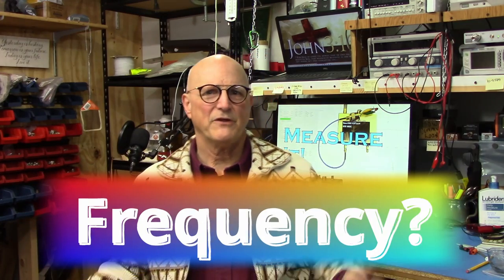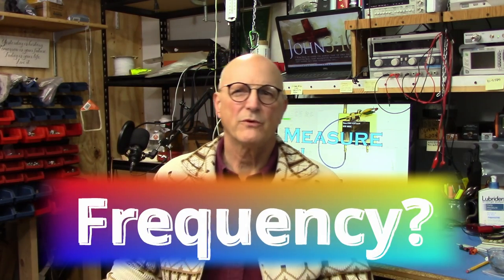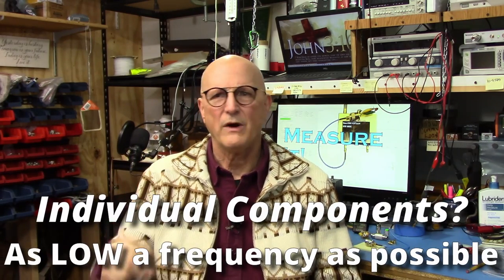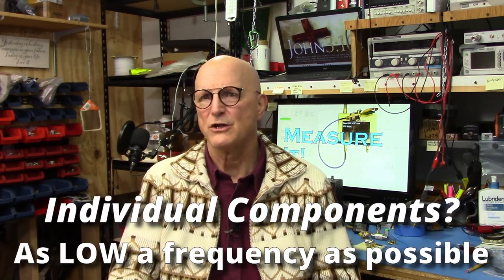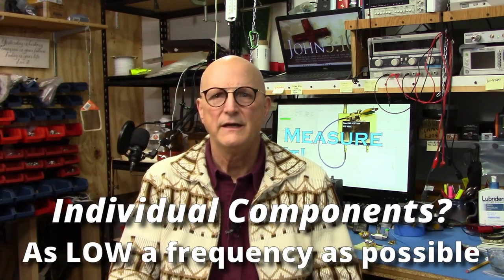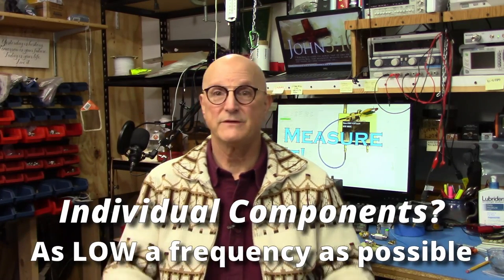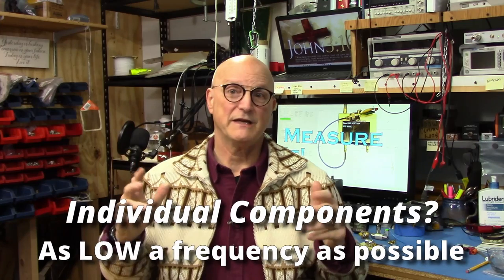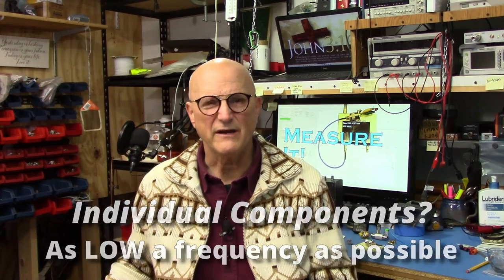Well, the next thing we have to think about is the frequency that we're going to use to make our measurement. If we are measuring individual components and all we want to know is their particular value, then we would likely want to perform this measurement at as low a frequency as possible in order to avoid the effects of parasitic stuff and the associated self-resonance of the component.